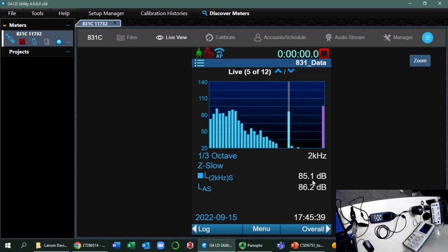Am I making sense? So they have their way of calibrating so that the number on the dial complies with ANSI standards. And of course, the step size is 5 here, but when they calibrate, I think they can go down to 1 dB. Yeah, with their special password, they can do that. So that's how they calibrate audiometers for clinics. And for the lab, we have the passcode for this machine, so we can do that. But I don't use the supra. The insert is within calibration. I think that's because I applied the calibration factor many years ago. And the supra is not complying because I don't care. I'm not using it. Does that make sense?